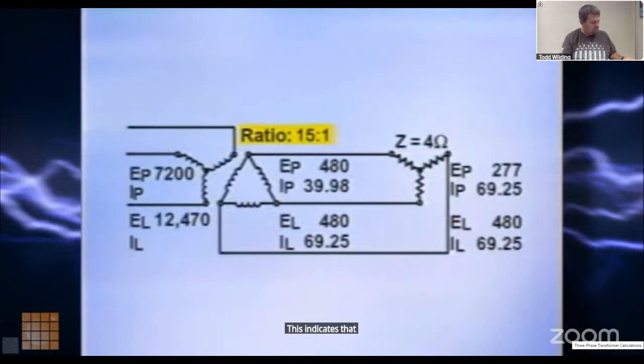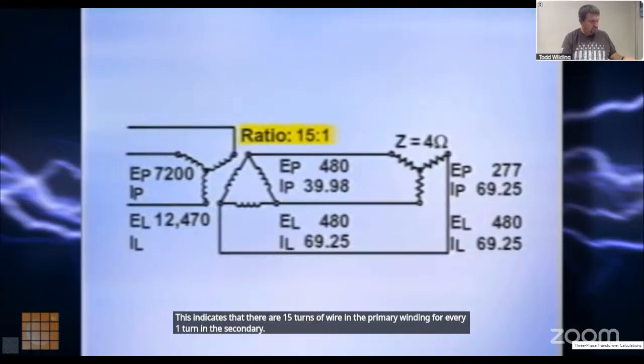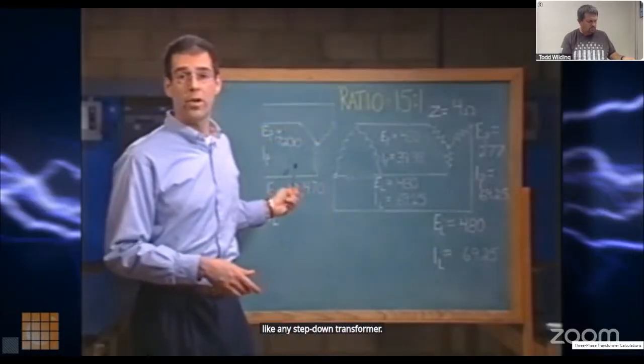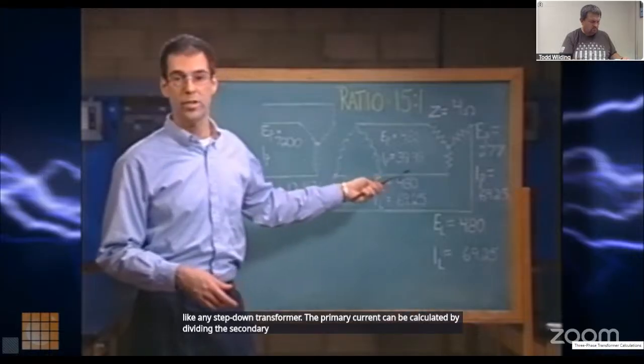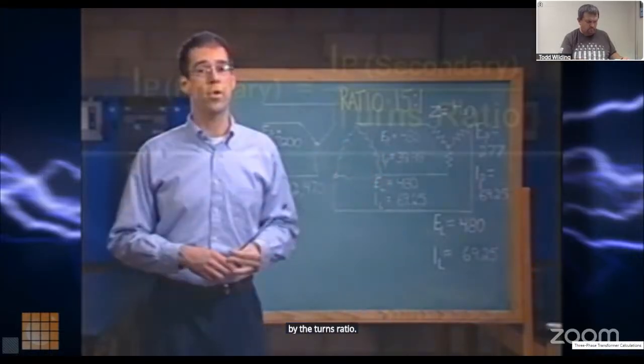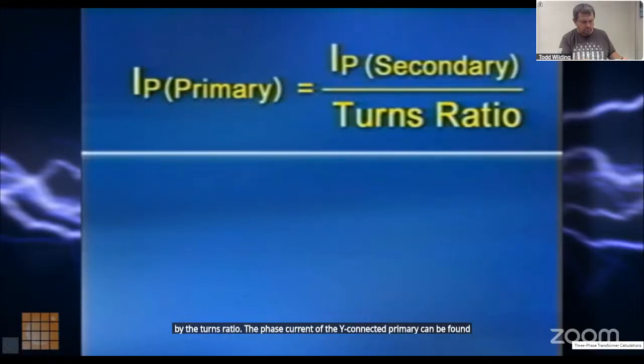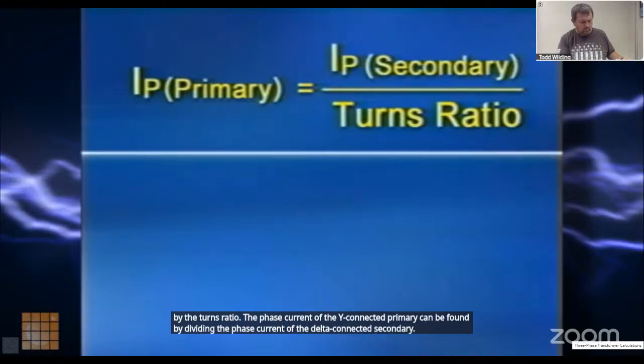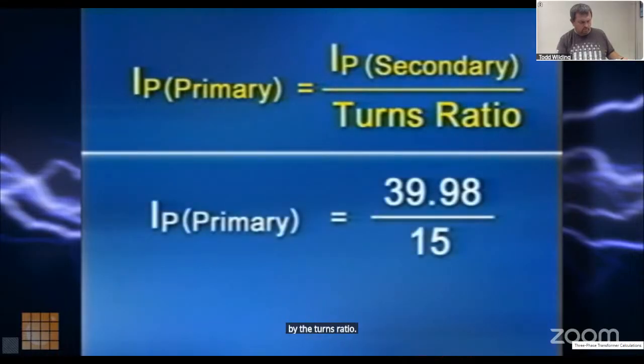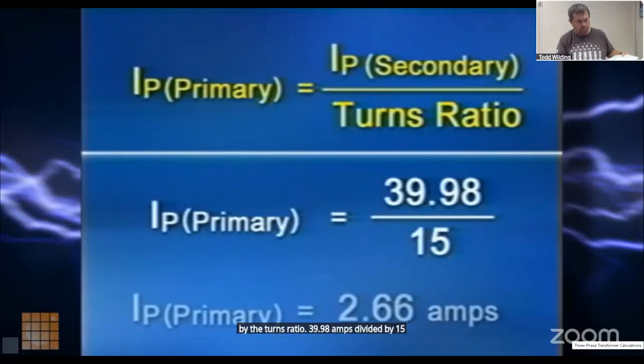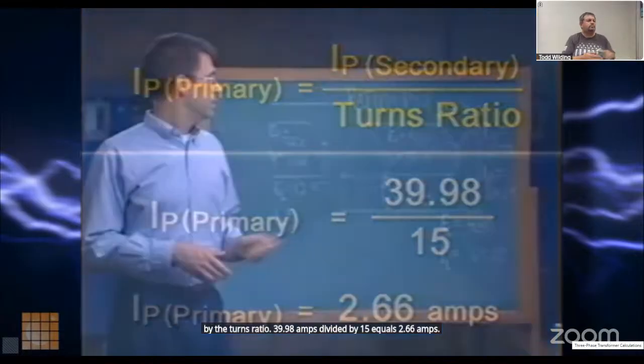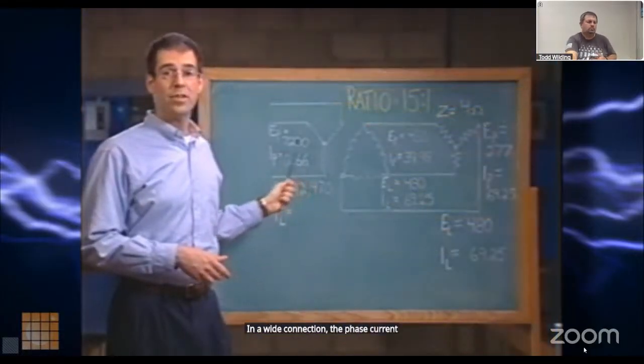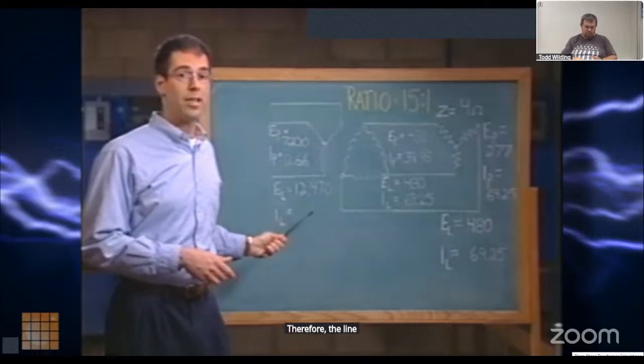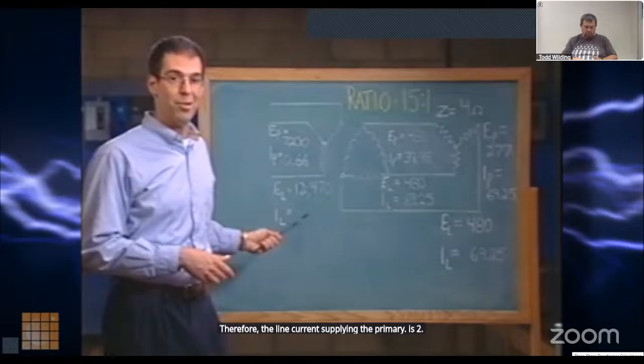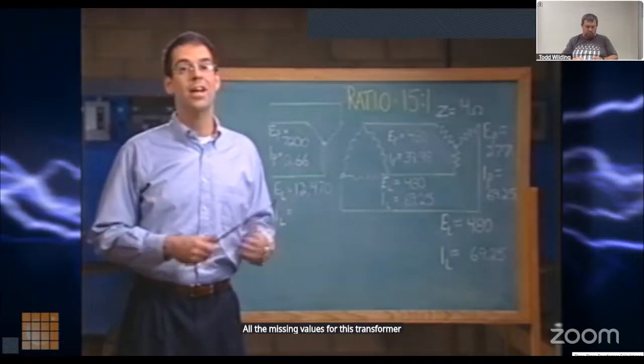This indicates that there are 15 turns of wire in the primary winding for every 1 turn in the secondary. Like any step-down transformer, the primary current can be calculated by dividing the secondary current by the turns ratio. The phase current of the Y-connected primary can be found by dividing the phase current of the delta-connected secondary by the turns ratio. 39.98 amps divided by 15 equals 2.66 amps. In a Y connection, the phase current and line current are equal. Therefore, the line current supplying the primary is 2.66 amps also. All the missing values for this transformer and load have now been determined.